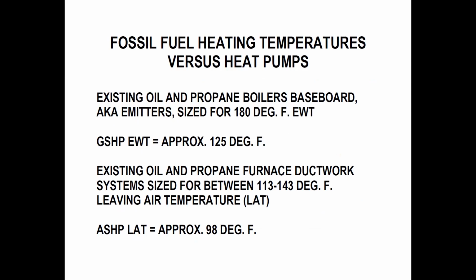All right, fossil fuel heating. This is one of the problems with converting an existing structure to heat pumps: your propane or your fuel oil, I don't think anybody here has natural gas, propane, fuel oil, or even your pellet boiler, if you have pellet boilers, which is the case for our New Venusa neighborhood and other places, including the library, those systems can get 180 degree water or much higher air. We're talking about 180 degree water. Heat pumps can only get you 125 degree water. Well, it can get a little higher, but I size my delivery systems for 125 degree water.